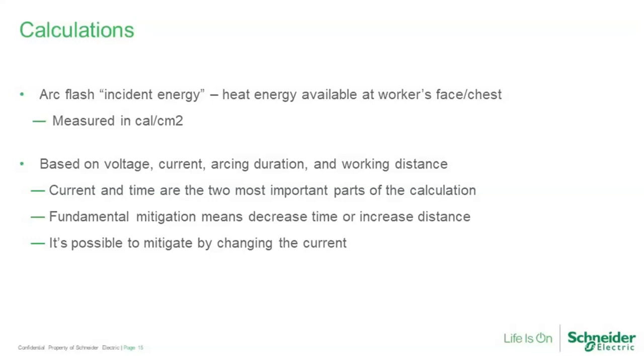Is it possible to mitigate by changing the current? Maybe. There can actually be some side effects from that. We've had discussions with folks that said, oh, we have high arc flash levels, I want to reduce my incident energy levels, let's put in a current limiting reactor or something like that. Well, when we do that, you run the risk of actually increasing the time that it takes for your protective device to respond, as the lower fault current may mean that it takes longer for a device to operate.